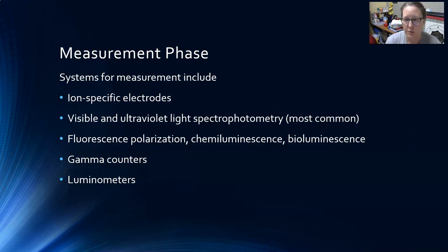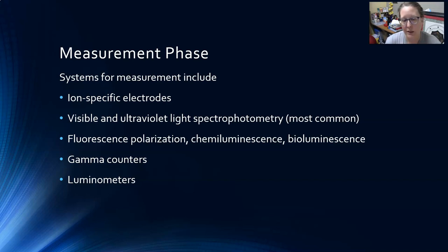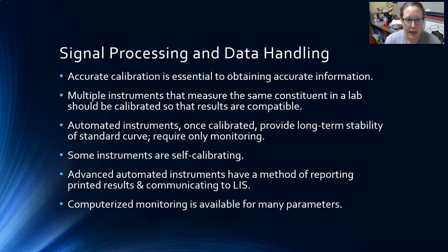In the measurement phase, there are different systems depending on the type of reaction occurring. We have ion-specific electrodes for many of our electrolytes, and visible and ultraviolet light spectrophotometry, which is the most common. On the immunoassay end of things, we have fluorescence polarization, chemiluminescence, bioluminescence, gamma counters, and luminometers.